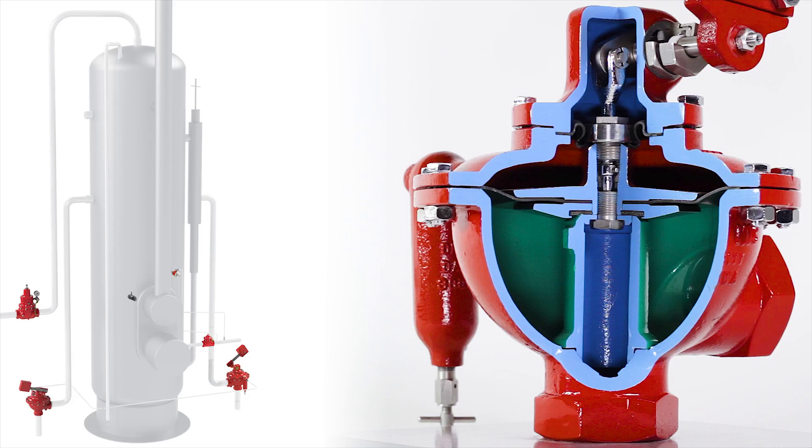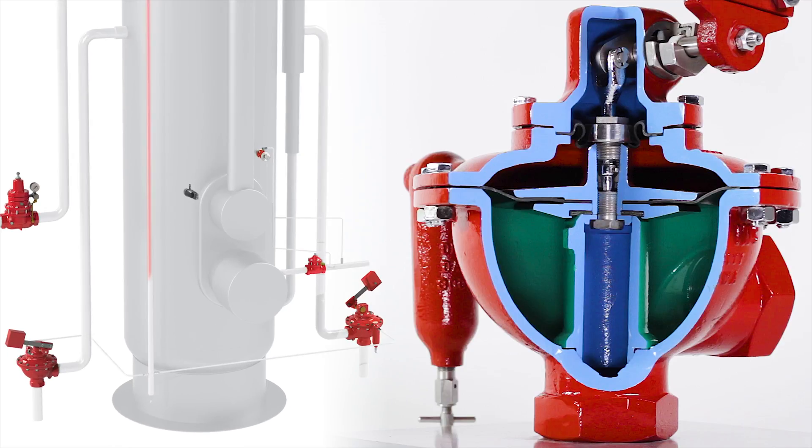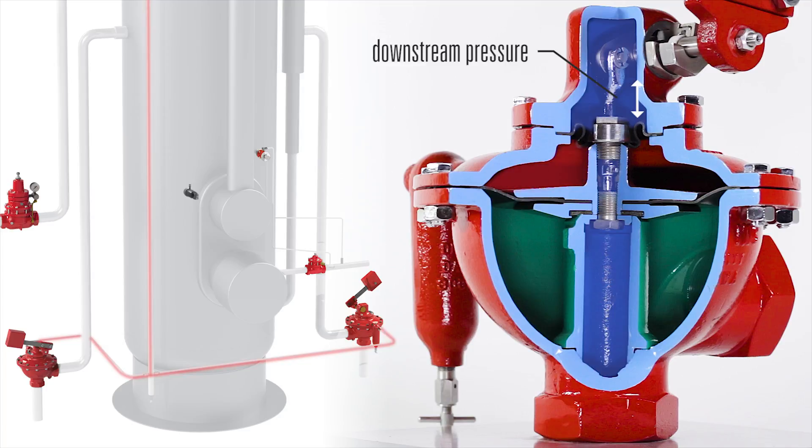In pressurized vessels such as treaters and free water knockouts, a gas equalizing line must be installed to ensure proper operation of the valve by equalizing the vessel pressure and valve pressure.